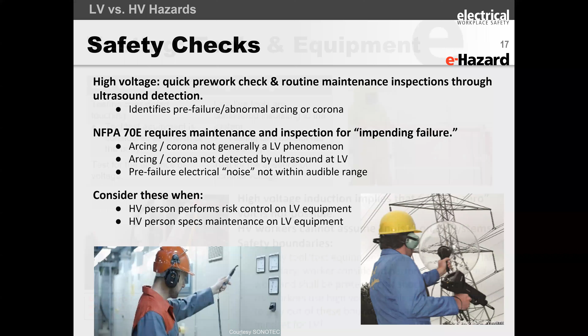At low voltage, testing is considered touching the equipment. When I take meter probes, as you can see in the bottom left picture, and hold the voltage probe, those pieces of equipment are physically considered an extension of my body. That means when I measure for voltage at low voltage, I am considered part of the system.